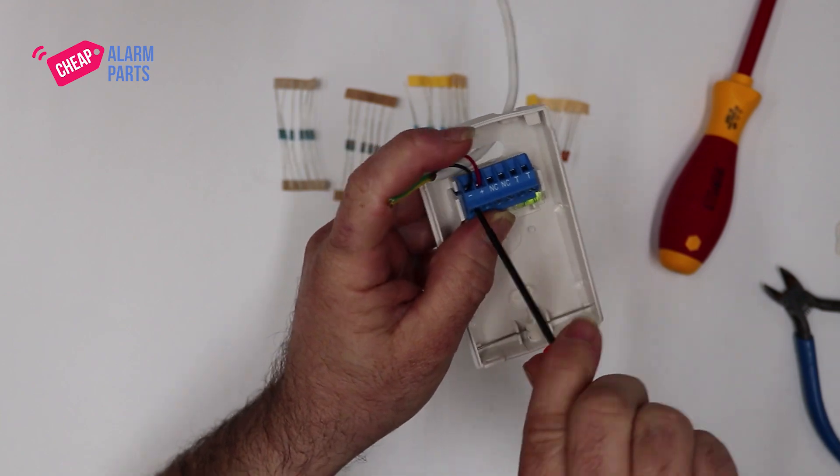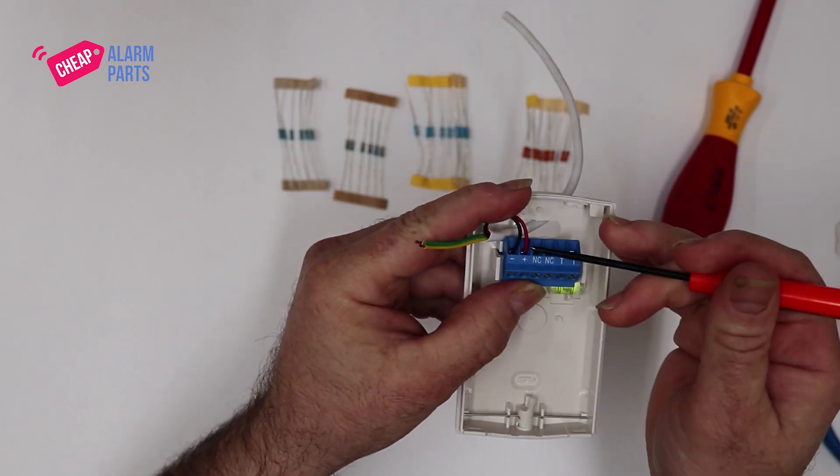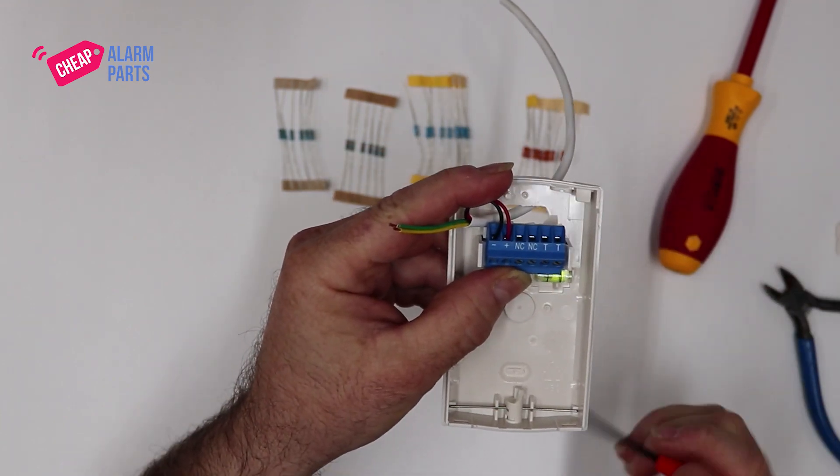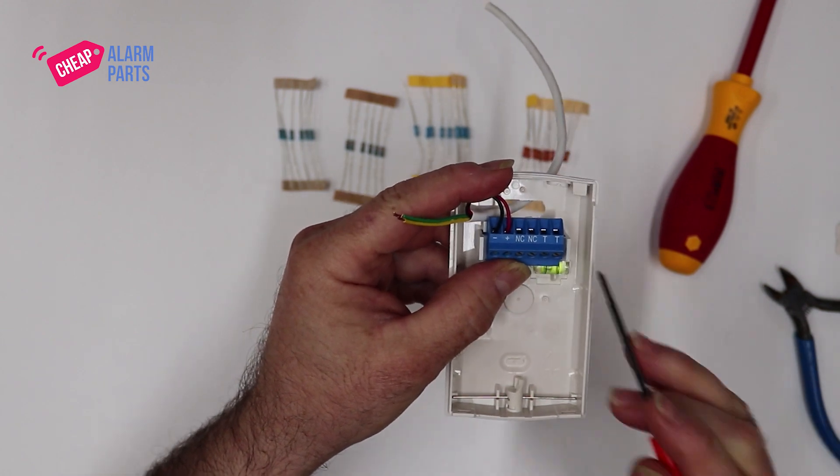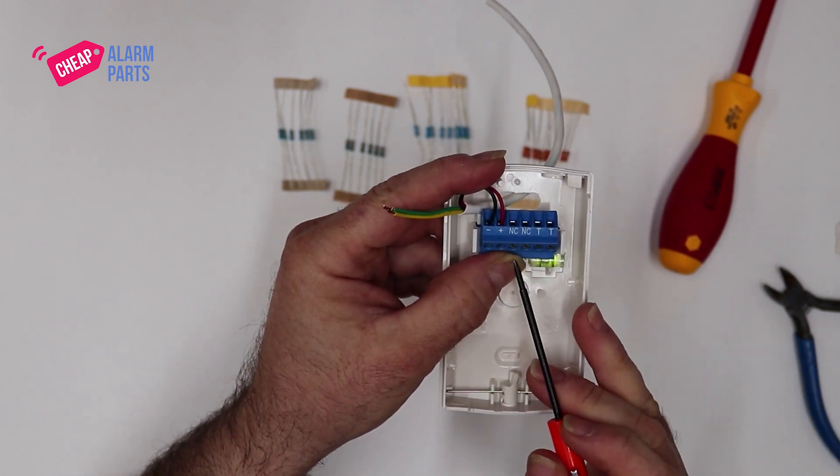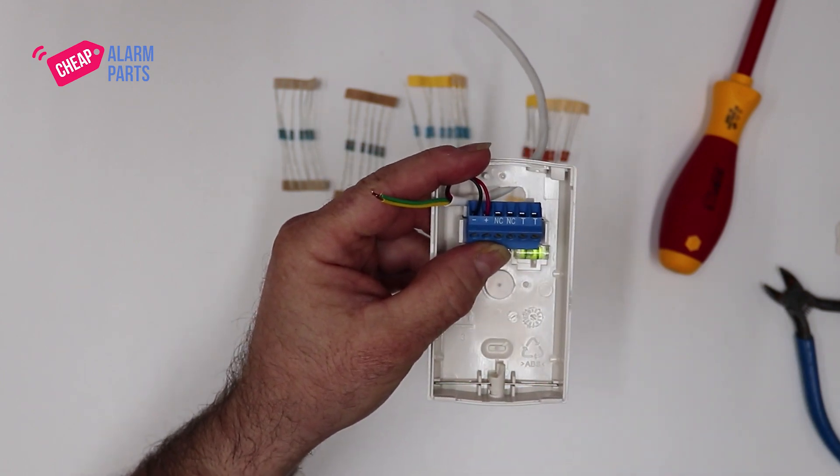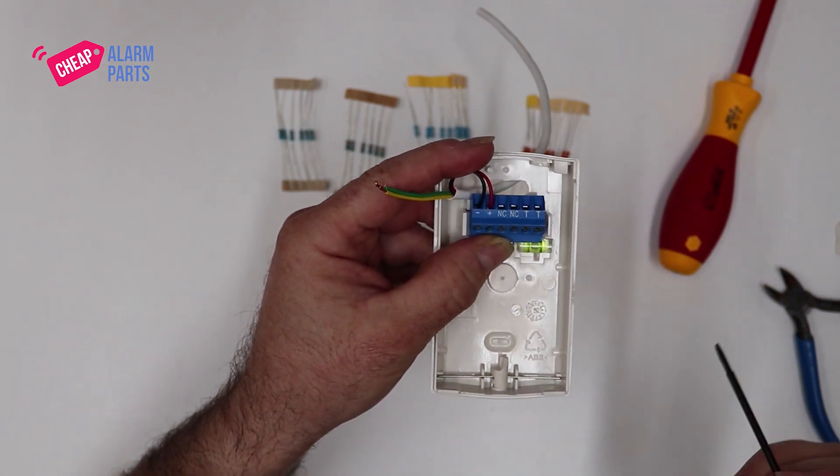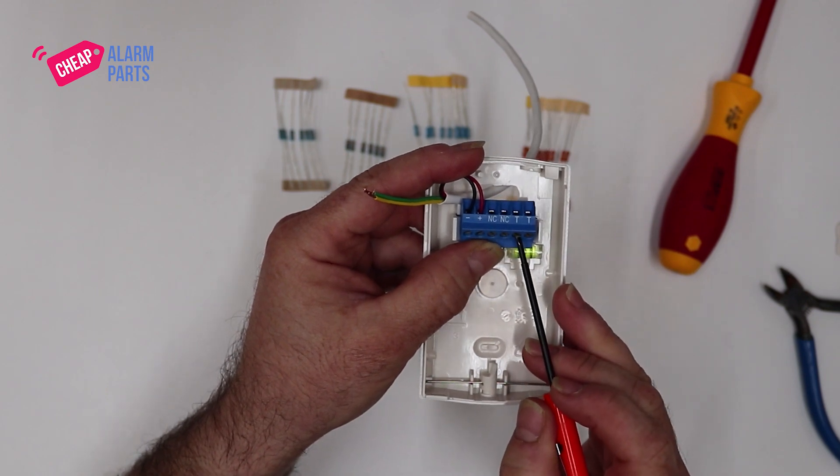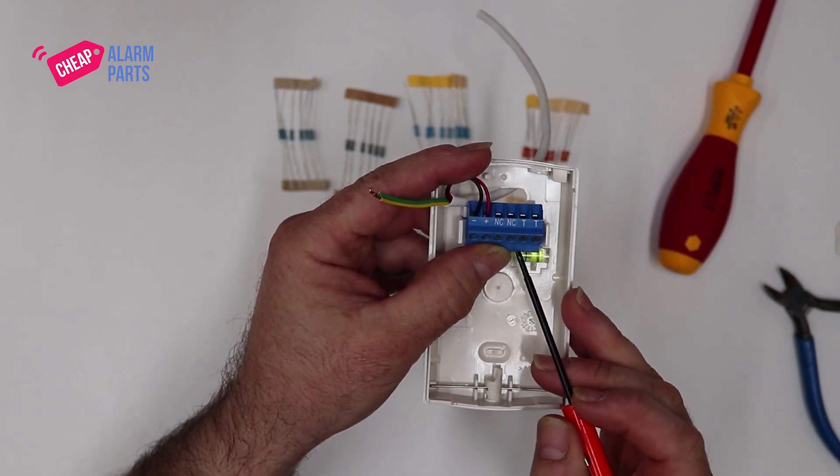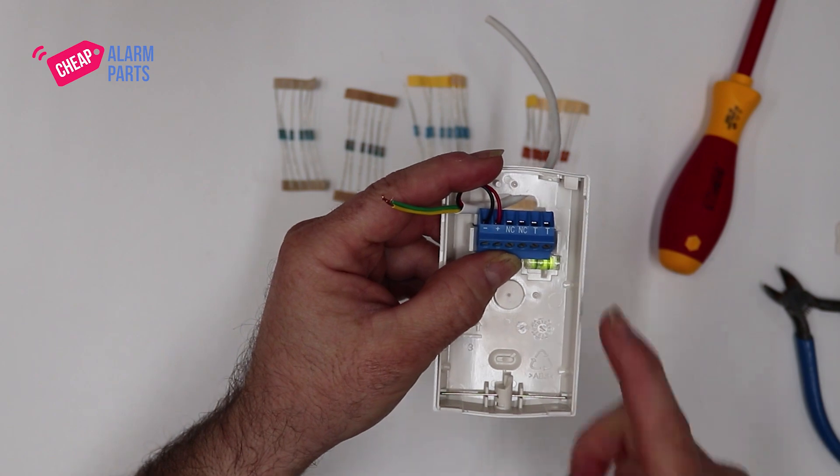Also, when you're done, make sure there's no little bits of copper sticking out of the terminals which could cause a problem later. Now, the next two terminals are the alarm contacts. These are normally closed when there's no movement and they open when the sensor sees movement. The next two terminals are the tamper contacts, and this tells us if the sensor is still attached to the back unit.